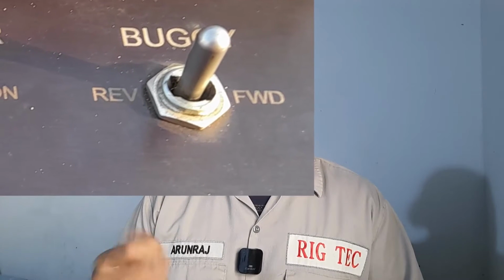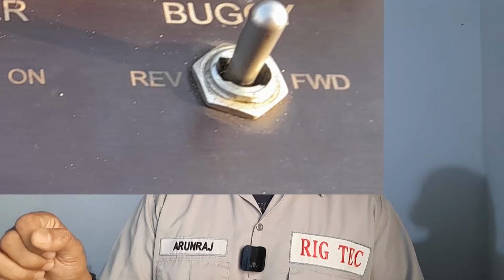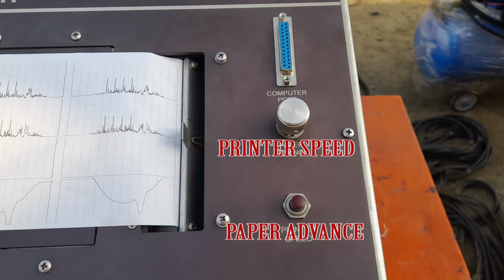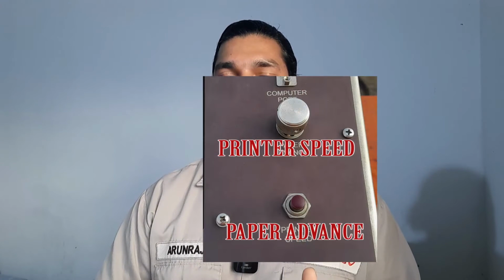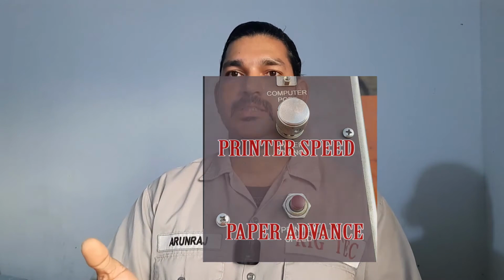When you are going to run, you should start in this order: first the coil, second the printer, and third the drive. The drive toggle switch can act as forward and reverse because it is a two-way switch. The right side is forward and the left side is reverse. Next is the paper control or chart control. The push button will help you release the chart paper, and this potentiometer will help you adjust the speed of the chart. You can run the chart in fast or slow condition.